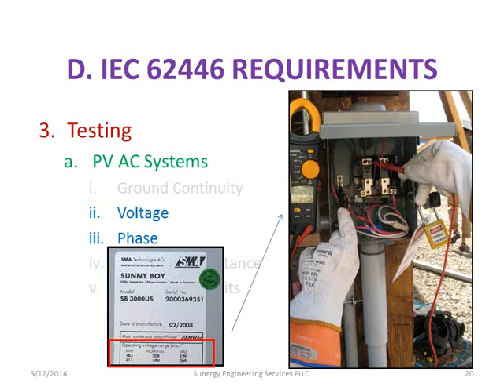And another requirement from the IEC is insulation resistance, which is actually a test to test how good the wire is, how good the insulation on the wire is. If the wire's been nicked in a piece of conduit, or particularly over time, if a wire has a tight bend going into a metal box and they didn't leave enough extra wire for expansion and contraction from heat, that wire can get pinched over time and it'll get grounded and it'll cause a problem.